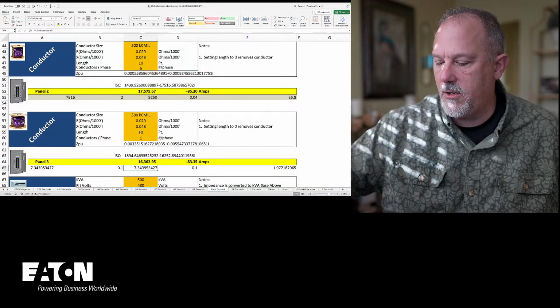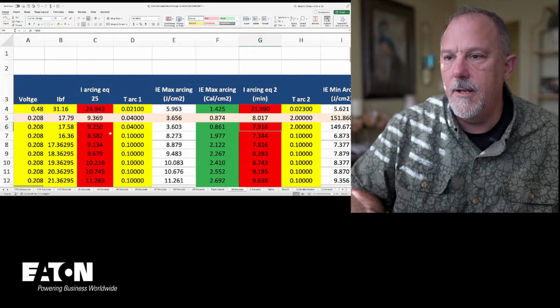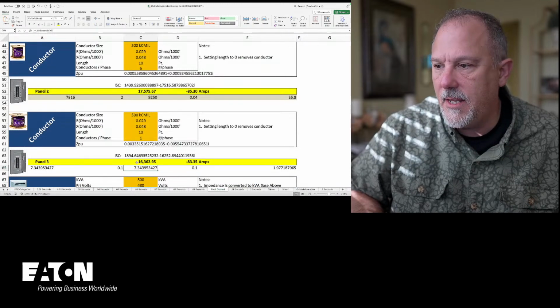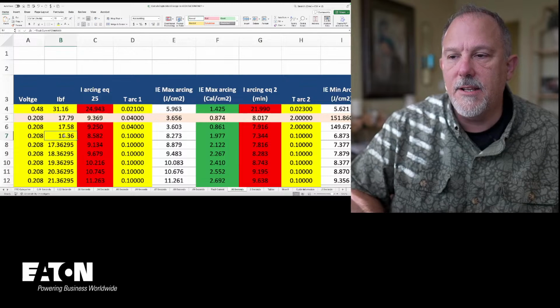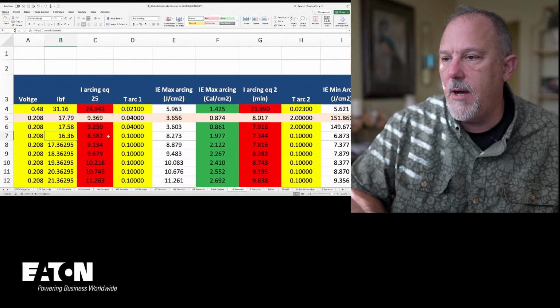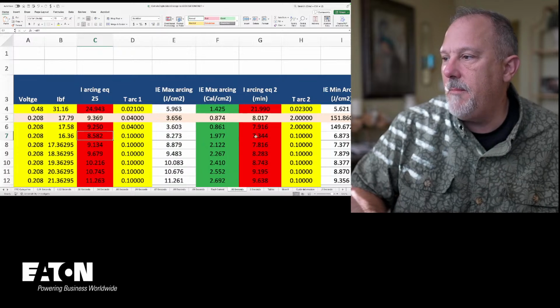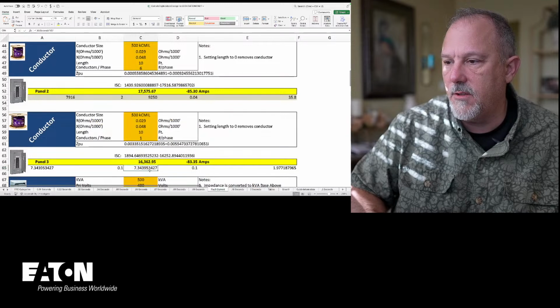So let's go back over to our spreadsheet, over to the 10 seconds. 16,362. My two arcing currents: my minimum is 7,344.